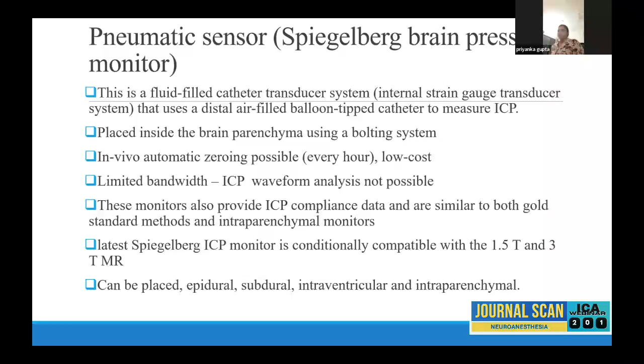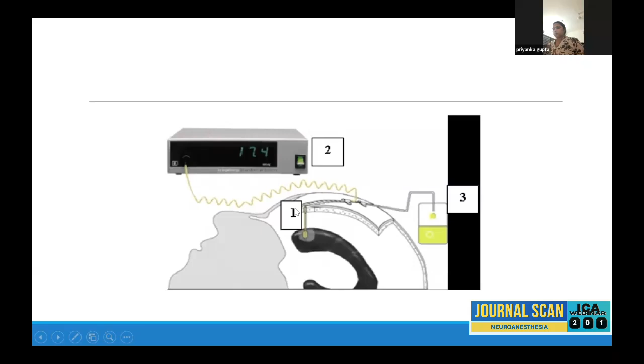And the tip of the catheter is an air-filled balloon. It is placed commonly in the brain parenchyma, using the same bolting at Kocher's point and burr hole, and inserting it. And every hour, the zeroing happens, the pressure transducer being near the monitor. Every hour there is an automatic zeroing possible. It opens to the atmosphere. So zero drift is minimized. But because of the limited bandwidth, ICP waveform analysis is not possible. These monitors also provide data about ICP compliance that are similar to the other standard methods and other intraparenchymal monitors. And these monitors are also compatible with 3T MRI. So here, this Spiegelberg is placed intraventricularly. Here it can be drained like an EVD, and this is connected to the monitor.